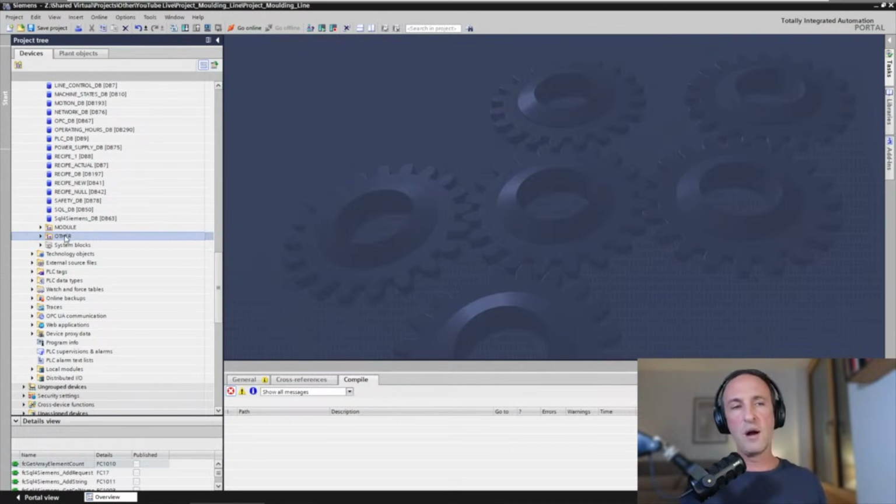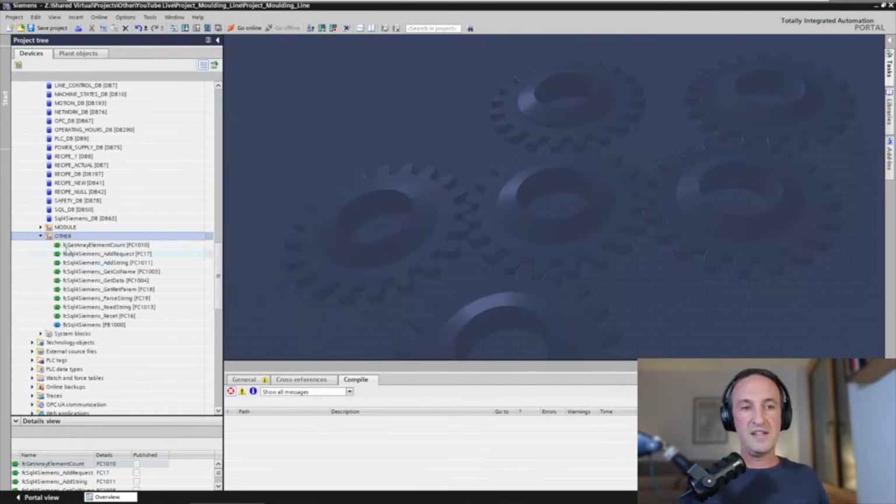A couple of weeks ago, I was on a commissioning and someone thought it was a good idea to call every group module 1, module 2, module 3, module 4, which of course made it difficult to figure out what was in the modules. So I had to go in, check out the logic, and I renamed the groups and reorganized the software to make it easier to read.